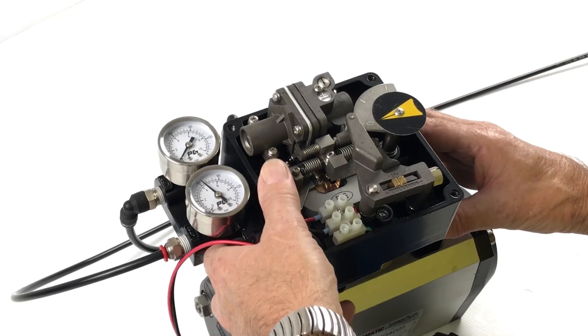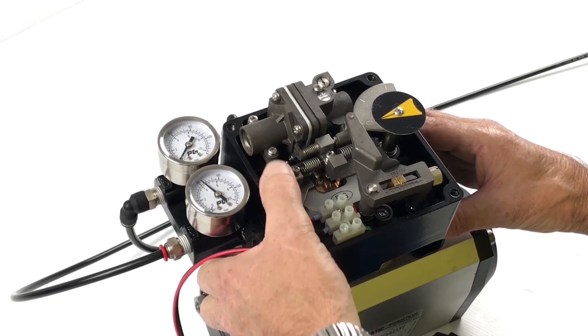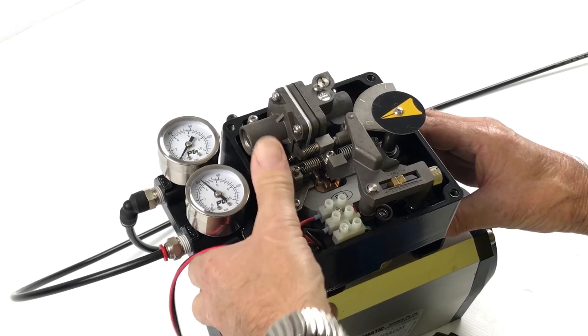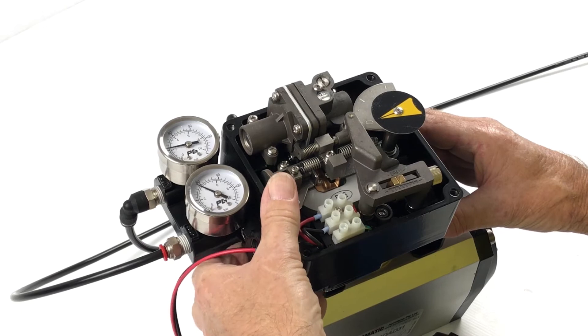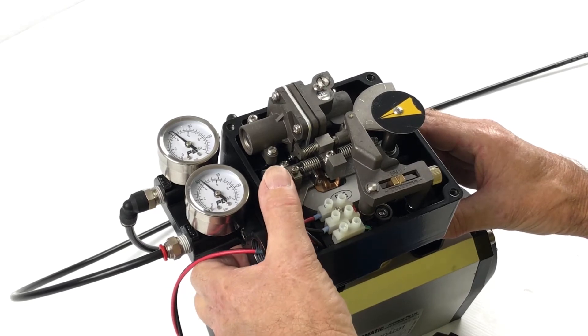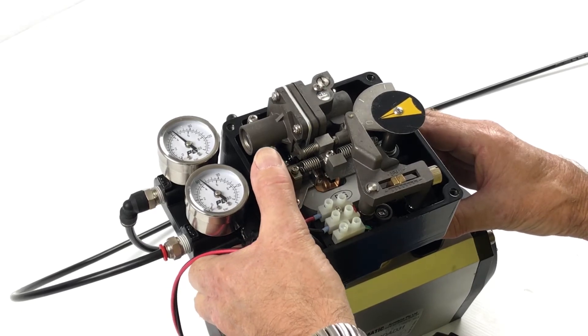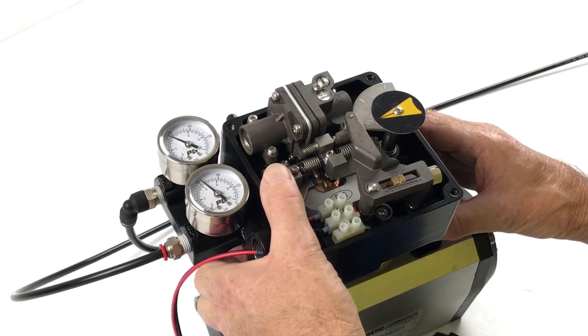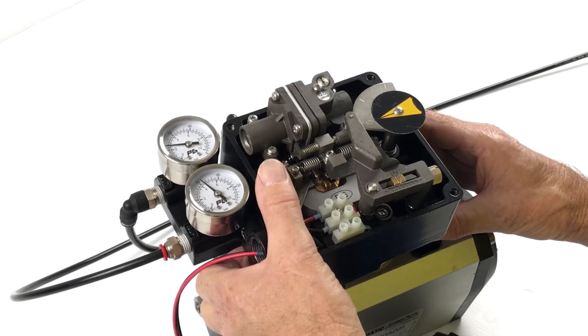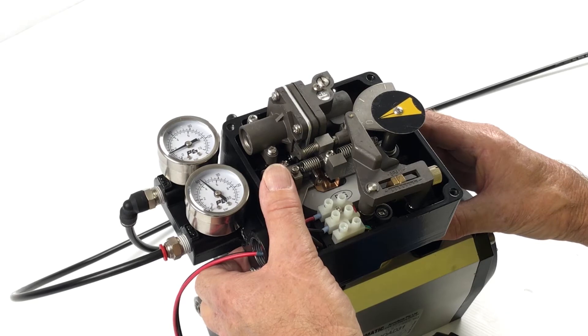So we're going to adjust the zero and then just retract it so the gauge just slowly drops away. It goes to zero. A quick drop means your zero is probably too far away.